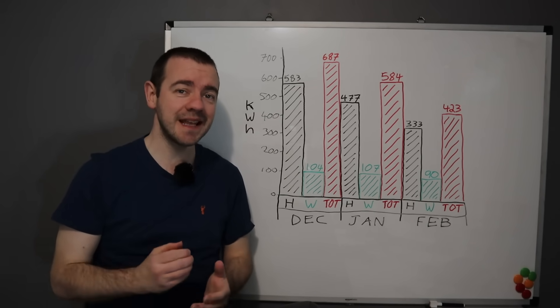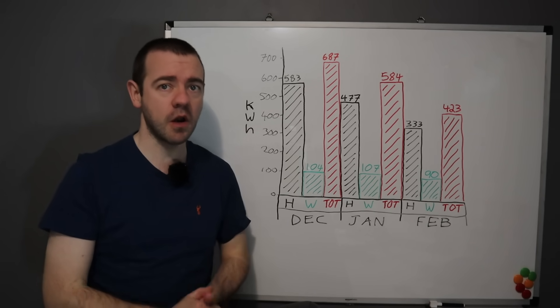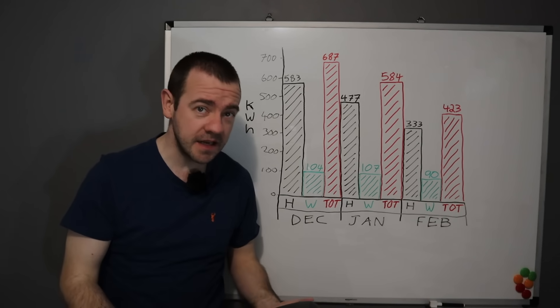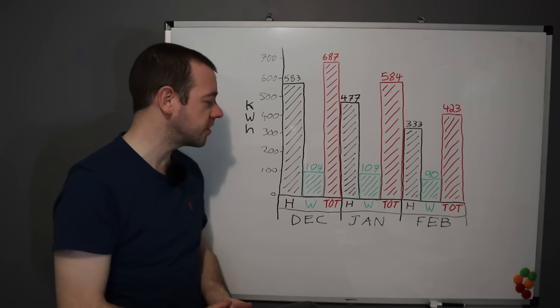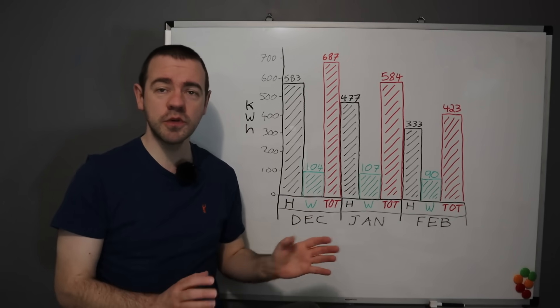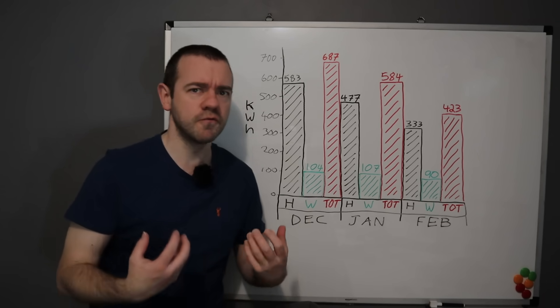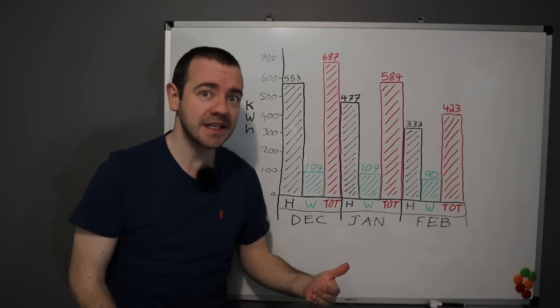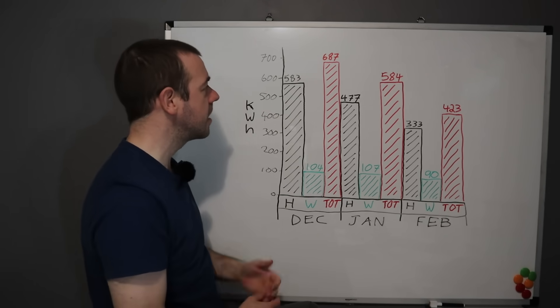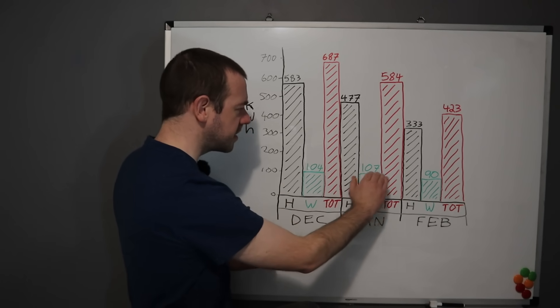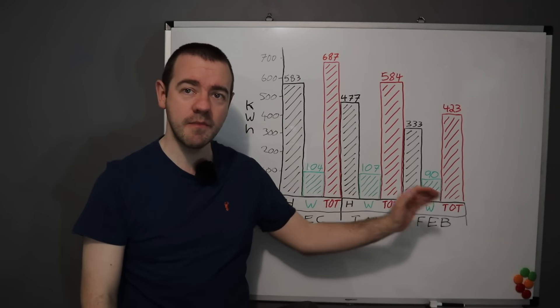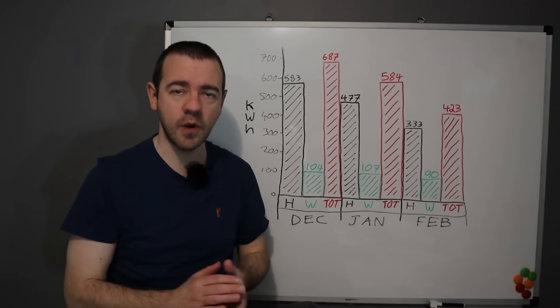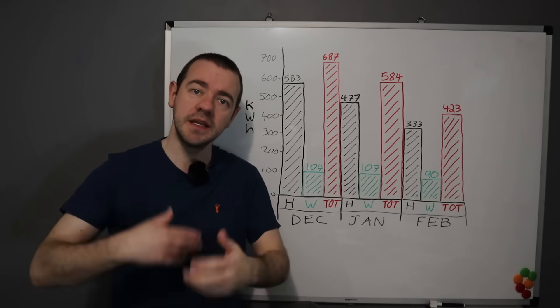And in total, so the red bars, the important one, 687 kilowatt hours in December, 584 in January, 423 in February. Now it should be pointed out that December was very, very cold in the UK, or at least for the UK. Minus 10, minus 15 I saw it for a few times up here in North Yorkshire. And for a good two or three weeks we had, as I said, for us, really cold winter. So it had a very, very good test.